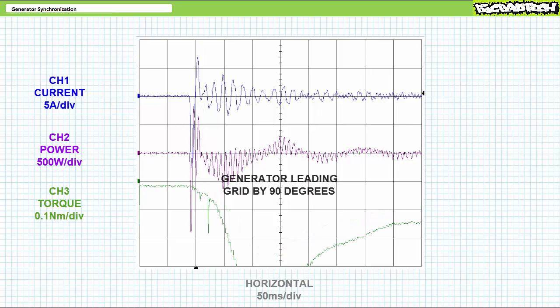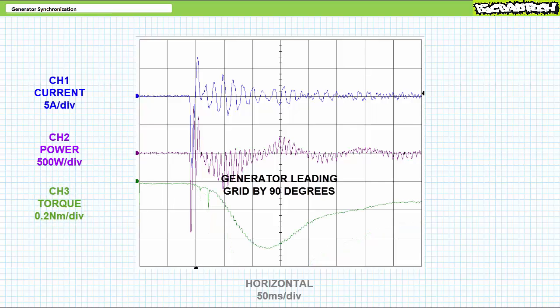Let's make it worse. Consider what happens when I close the contactor when the generator matches phase shift, frequency, and voltage magnitude, however the rotor is a full 90 degrees ahead of the stator at the time of closure. Electrically, there's a supermassive surge of current and electrical power out of the machine, and mechanically, the shaft experiences a large surge of counterclockwise braking torque. So large, in fact, we've jumped off the O-scope screen at our present scale. When I rescale it to 0.2 Newton meters per division, looks like we're just shy of negative 0.5 Newton meters braking torque. Vicious indeed, and not a recommended practice. A greater and greater mismatch results in longer and longer durations of undesirable electrical and mechanical transients.